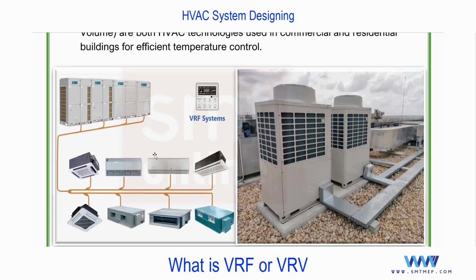You can find on screen also, on the left side image. You see, consider this as one outdoor, one unit, and to which we can connect different types of multiple indoors, nothing but FCU or AHU. You see, these are all FCUs. And below we can call this is AHU, this is concealed AHU, and this is a cassette. So first point is, with one outdoor, we can connect to multiple indoors. And the second point is, the indoor can be of different types, which suits the interior requirement or the site condition. So we have a lot of flexibility in this. As per the interior requirement, if they ask for cassette or high wall or freestand or concealed FCU or a ducted AHU, we can use any of these types.